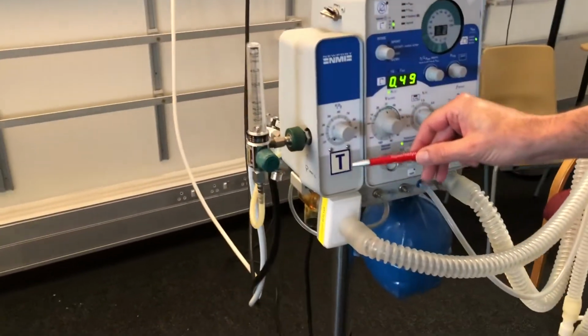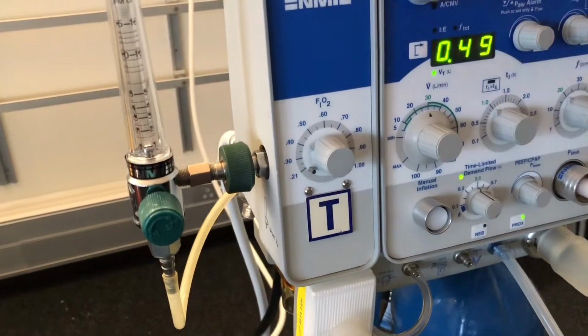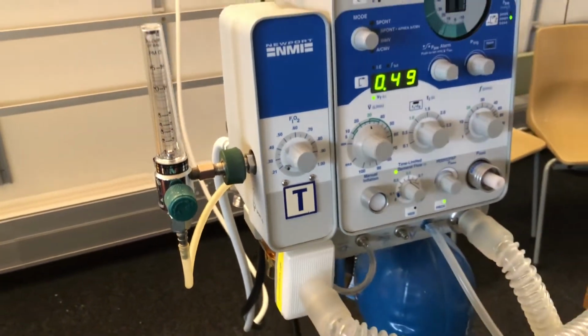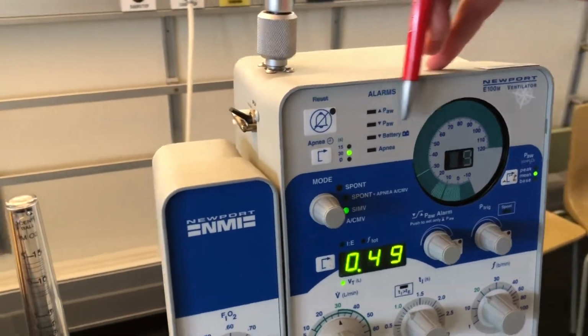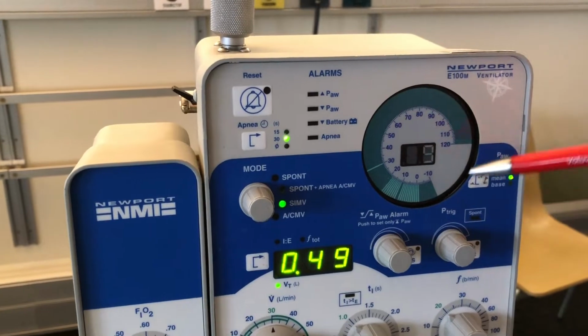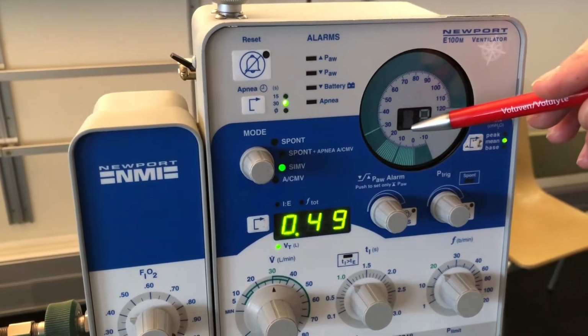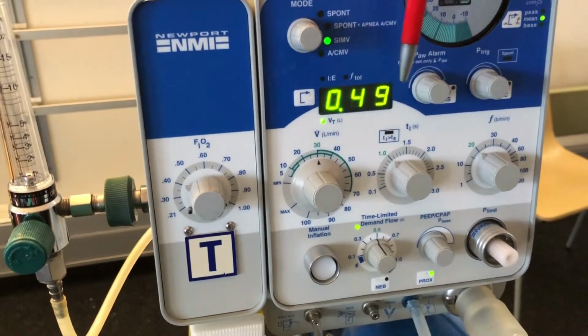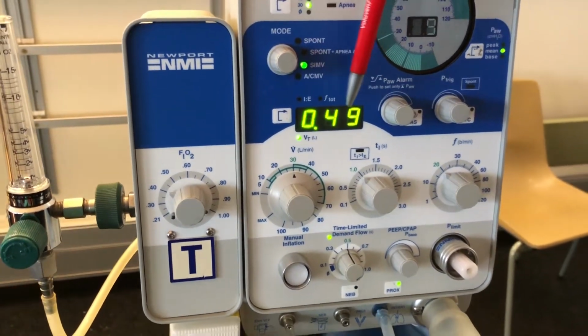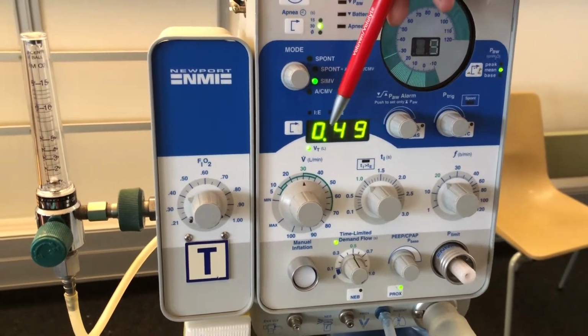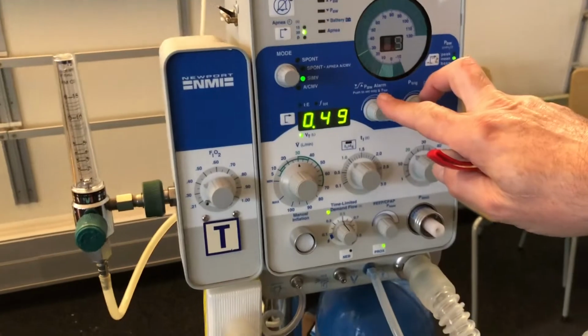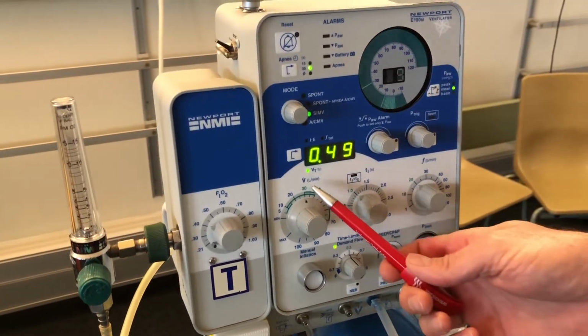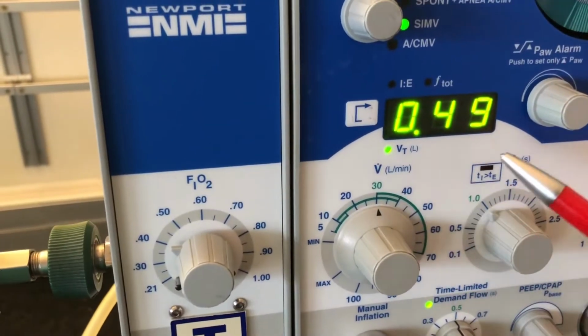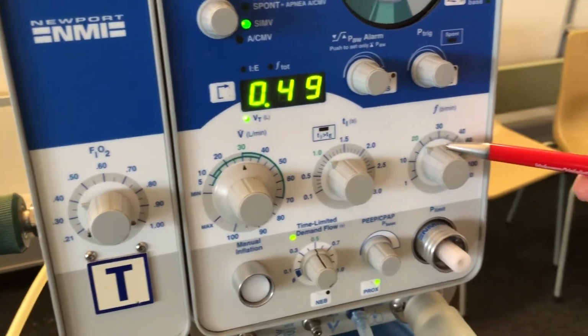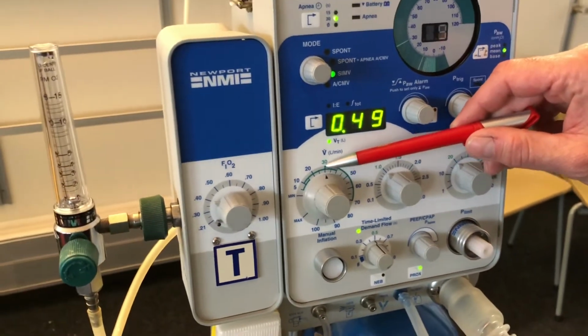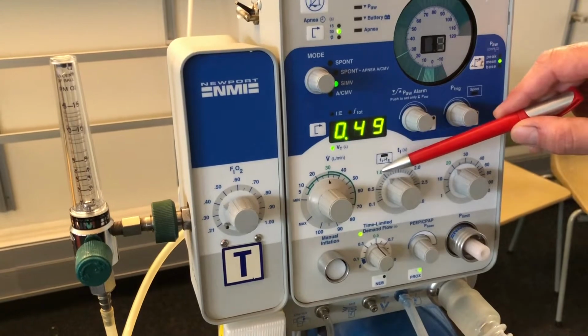On the left hand side of the machine here, we've got the dial for setting the FiO2 that the patient's going to get. And then in the main panel of the machine, we've got alarms at the top of the machine. We've got a pressure gauge which can read a number of different pressures for us. And then we've got a setting panel just below it, where the machine will tell us what the IE ratio, the total breath rate, and the tidal volume are for the patient. We can set alarm limits. We can set the inspiratory flow rate for the machine. We can set the inspiratory time and the total breath rate. And you'll see that the so-called normal settings for an average patient are highlighted in green.